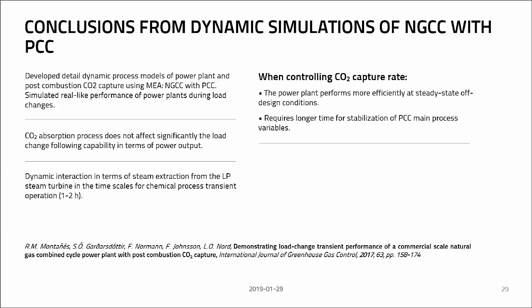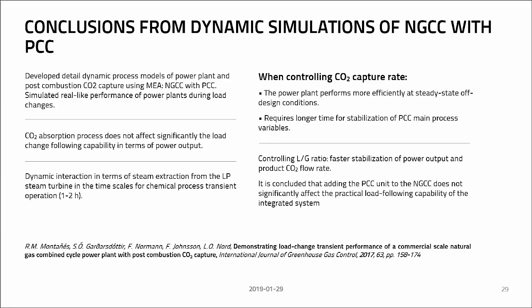But we also observed that when controlling the CO2 capture rate, the power plant performs more efficiently at steady-state off-design conditions, and it also requires longer time for stabilization of the capture unit main process variables. However, when we used liquid-to-gas ratio control, we found that the entire facility reached faster stabilization. It means the combination of the power output and also the CO2 product flow rate. And as a main conclusion, adding the capture unit to the combined cycle power plant does not significantly affect the practical load following capability of the integrated system.